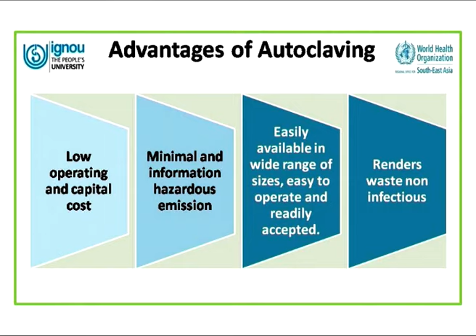The advantages of using an autoclave for treating waste are a low operating and a low capital cost. There is minimal or almost no hazardous emissions because we are not actually burning the waste. The autoclave has been used since time immemorial for the sterilization of equipment and so we have a wide range, a large variety of autoclaves which are available, which are easy to operate, which are also accepted by the medical community and it renders the waste non-infectious. But there are certain disadvantages for which the autoclave may not be used because it is not suitable for pathological and cytotoxic waste.